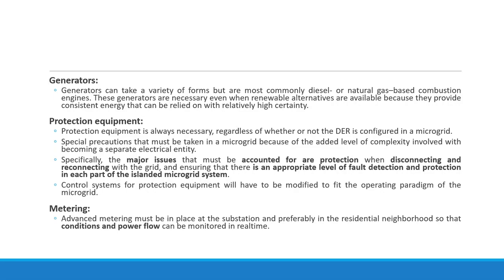Then protection equipment is required. The microgrid has controlling capability. It is going to control generator, load, etc. When there is a fault, there will be a rise in current. We need to protect equipment from this high fault current. The whole system must be protected basically. So protection equipment is needed. Protection equipment is always necessary regardless of whether or not distributed energy resources are configured in a microgrid. Whatever is the case, it is required.